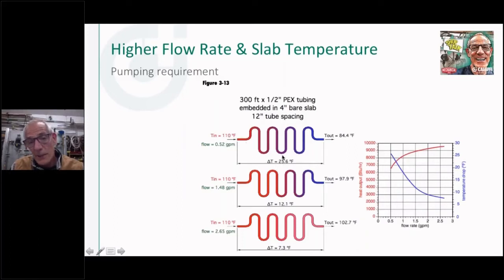And you can see exactly by the color of that loop what happens. So if you get down to this part of the room or this end of the loop, that's not going to be a very comfortable floor surface temperature there, because I've run in such a wide temperature differential there. So all right, let's take and squeeze it down. Same temperature here. I'm going to squeeze it down to a 12-degree delta T, and you can see I'm starting to even that out a little bit better.